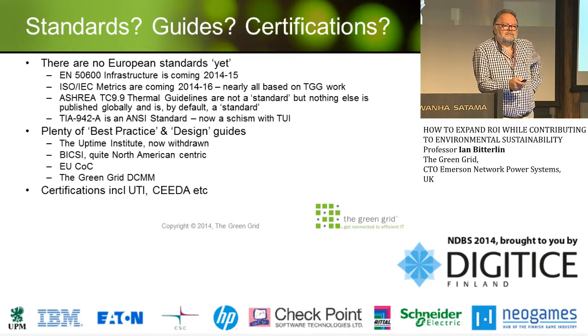As far as Scandinavia is concerned, there's a big impact from ASHRAE. ASHRAE TC 9.9 is certainly not a standard, it's a guideline, but it's the only guideline in the world that describes the thermal conditions for ICT hardware—temperature and humidity. My advice to everyone in Scandinavia is you better start thinking about features other than 'it's a cold climate,' because being a cold climate doesn't cut the mustard anymore. It doesn't give you any more competitive advantage than building a data centre in southern Spain, central Italy, or even the North African coast.